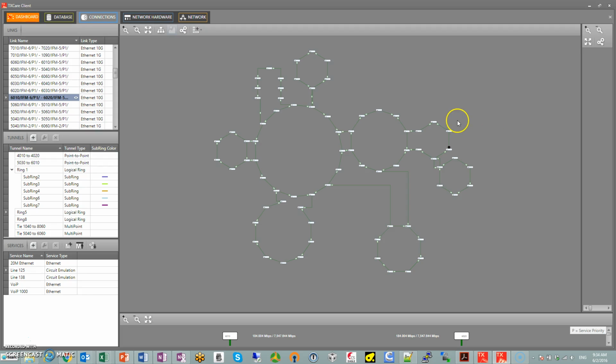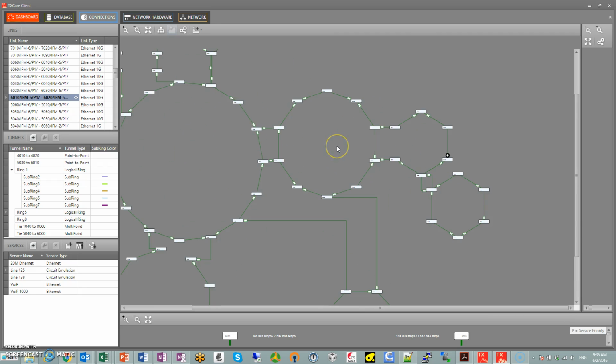So what does that mean? Maybe a large 20 node ring, or maybe a couple of rings. So in this case, why don't we create a service that has one RS232 port both at the main control center and the backup control center, so both SCADA systems, the primary and the backup, could poll simultaneously all of the RTUs, let's say the RTUs in this particular subnet right here. I'm sort of encircling here. It looks like some 15, 20 nodes or so.